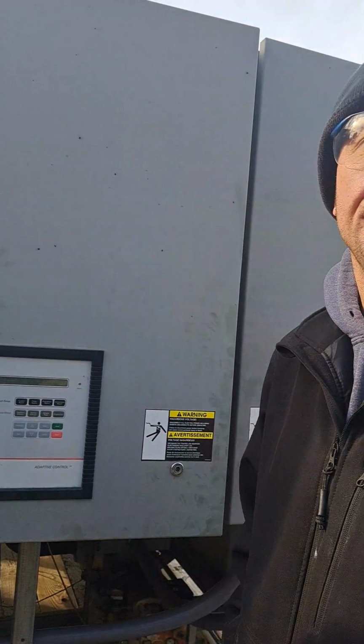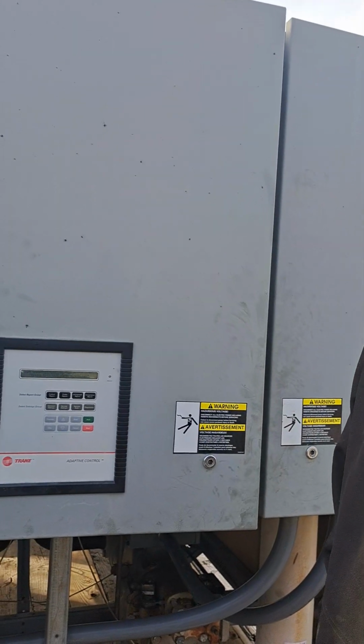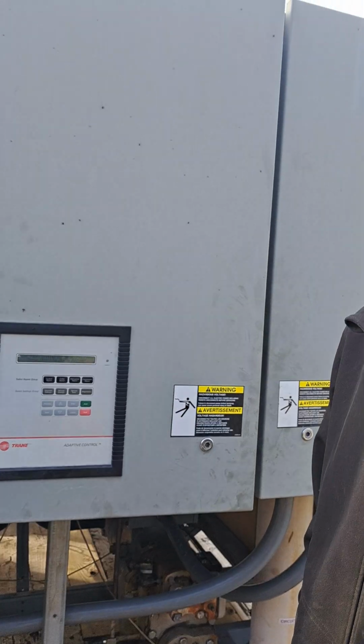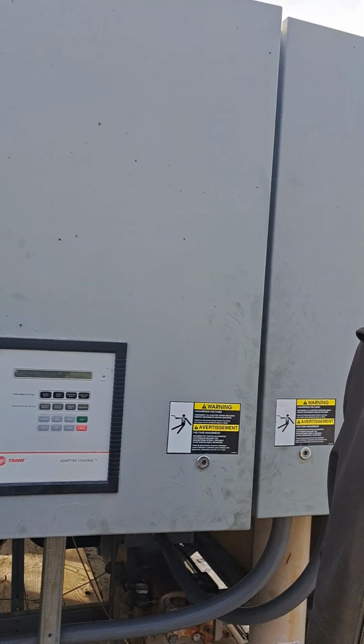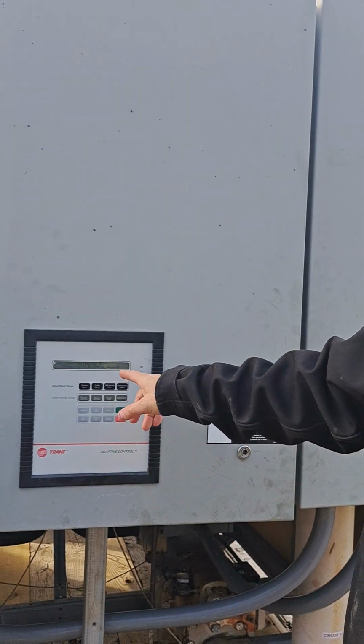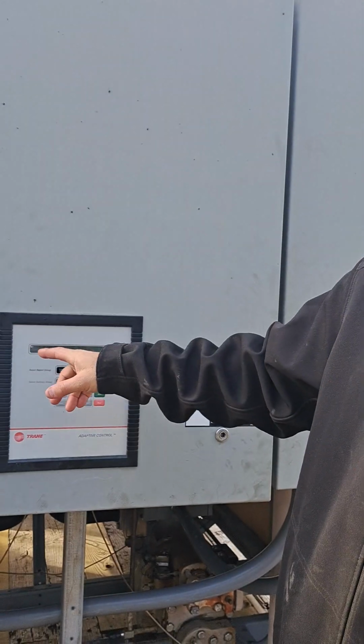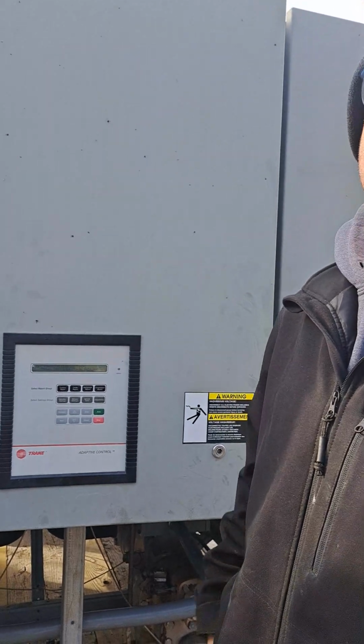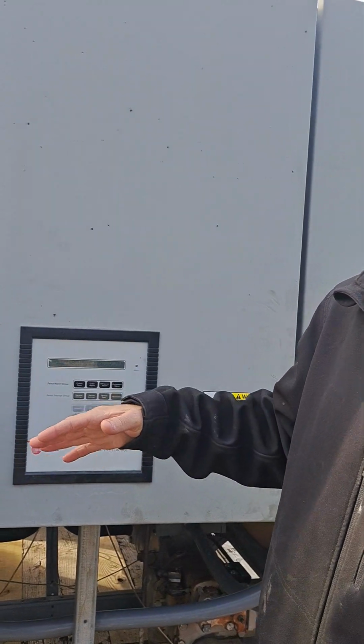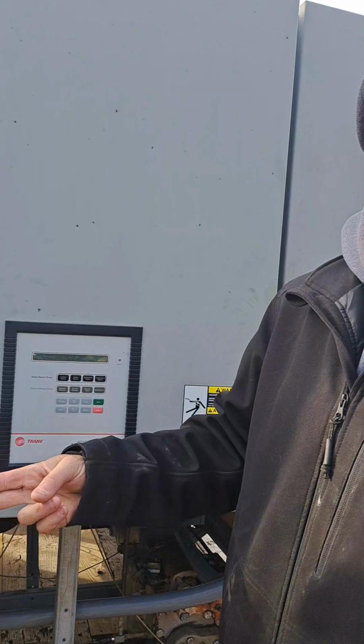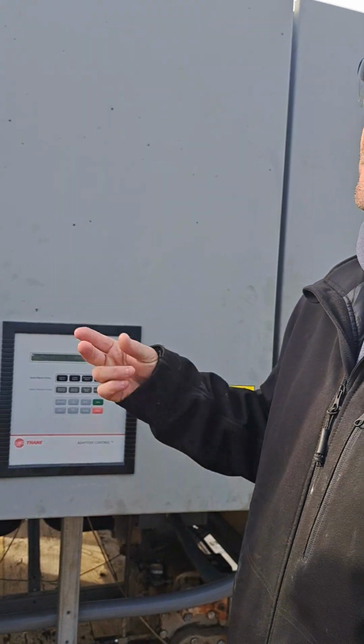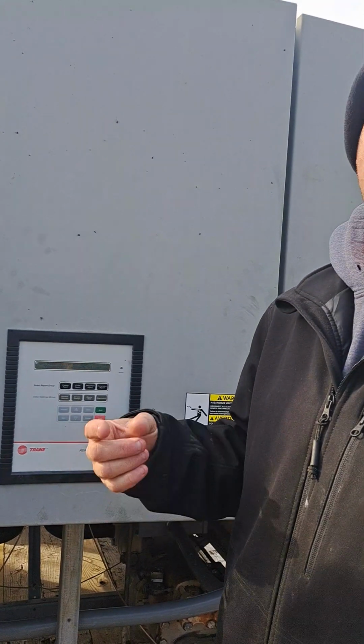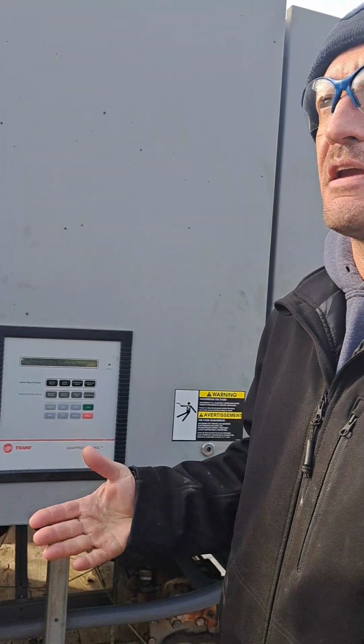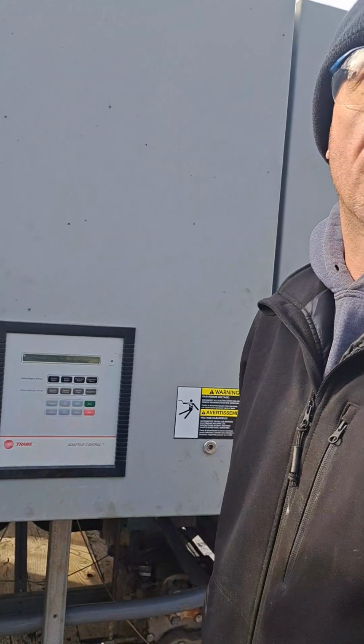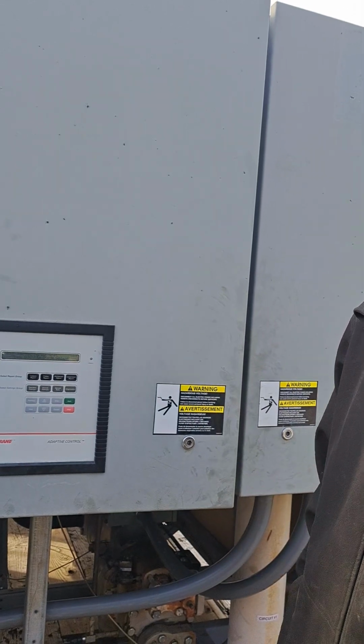And so we're set at 15 degrees. So that's 15 degree return. So the leaving temperature is going to be lower. You're probably seeing 9 or 10 degrees on your leaving temperature. Okay. So yeah, if you set this down to 10 degrees, it's going to be leaving at like 0. Okay. And then you're going to be bumping up against your safeties. So yes, because this has low pressure, low temperature safeties in it. So as it's monitoring all this stuff, it's trying to protect itself is what it's doing. It's trying to keep from freezing the barrel up and destroying the chiller. Okay. So that's what those safeties are meant for in here.